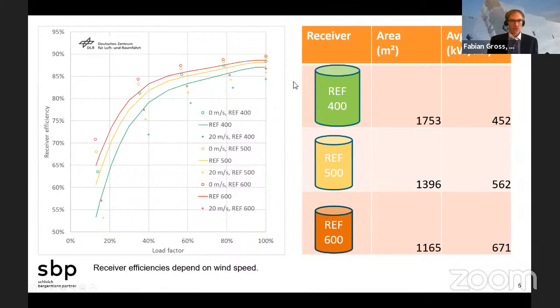As they have different surface areas, they also show different thermal efficiencies, shown on the left-hand side. The big green receiver has the lowest efficiency, while the small receiver shows the highest thermal efficiency. But for a total power plant, you need to think heliostat field and receiver together, since it's also more challenging for a heliostat field to hit a small receiver. So the optical efficiency is higher for the green one and lower for the small red one.